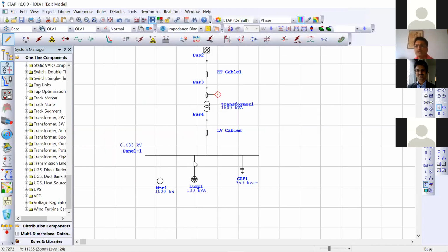So protection coordination can also be performed after this load flow, wherein you will verify whether device capabilities are as per requirement or not. Then the next step is short circuit analysis, by which you will know the short circuit levels at each and every bus, so the equipment capacity connected to that bus can be decided or designed.